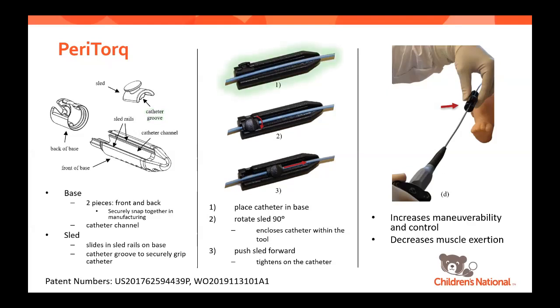To use the tool, the sled is pulled back and rotated 90 degrees to the left, opening the tool. The catheter is then placed in the channel, and the sled is rotated 90 degrees to the right, closing the catheter in the tool. The sled is then pushed forward until it is securely holding the catheter. The main channel is sloped so that the catheter groove and the channel converge as the sled is pushed forward, allowing the tool to accommodate catheters ranging in size from 3 to 9 French.